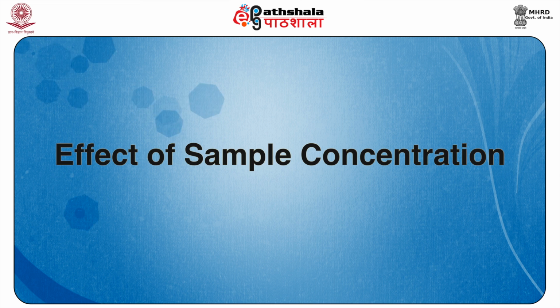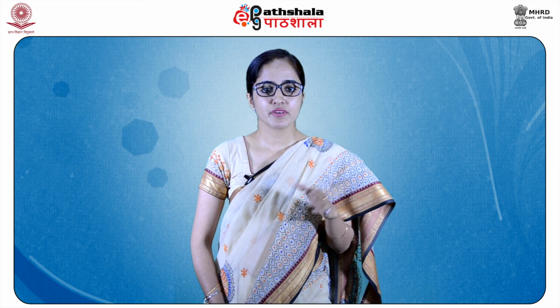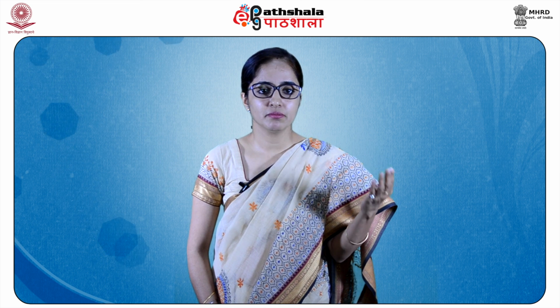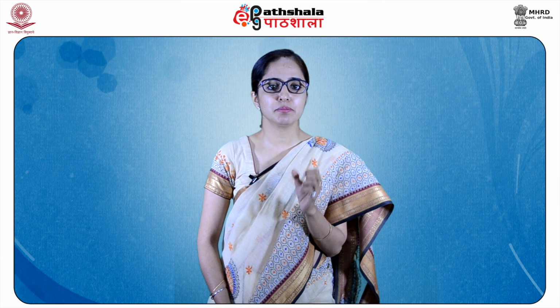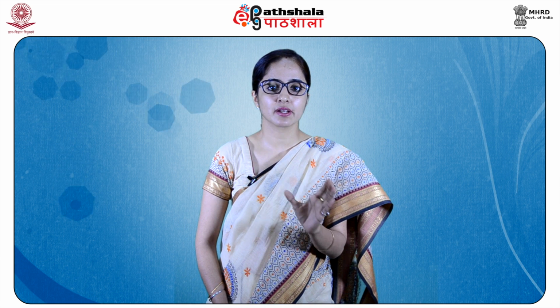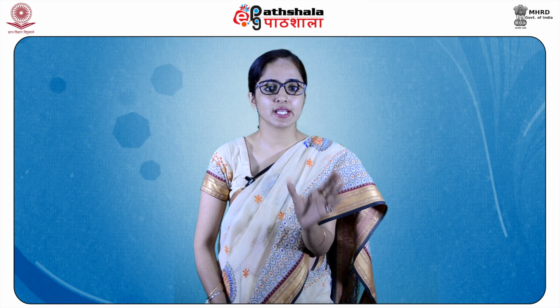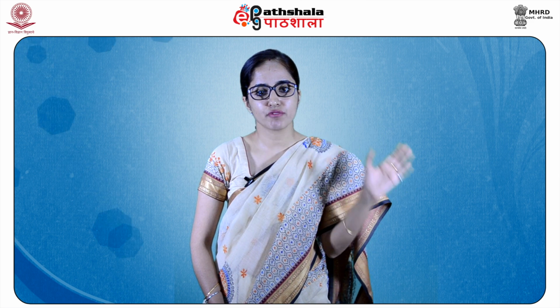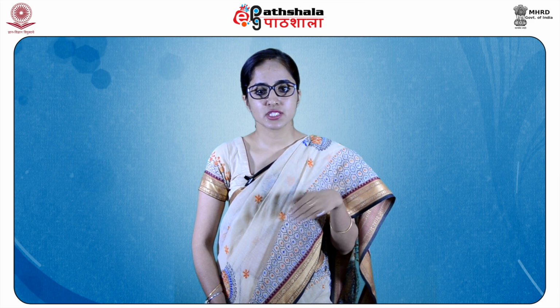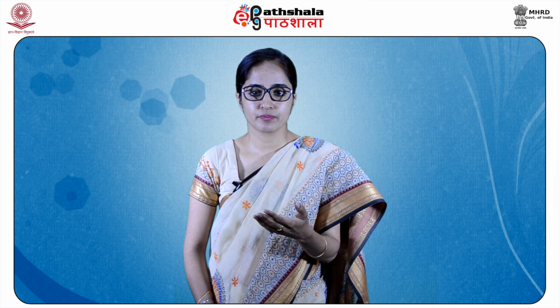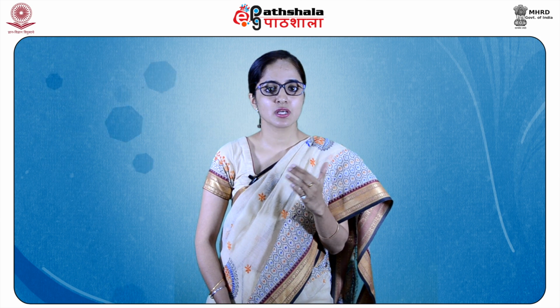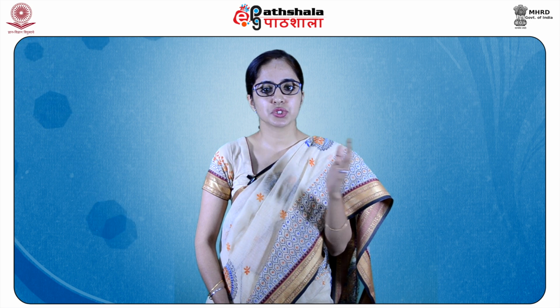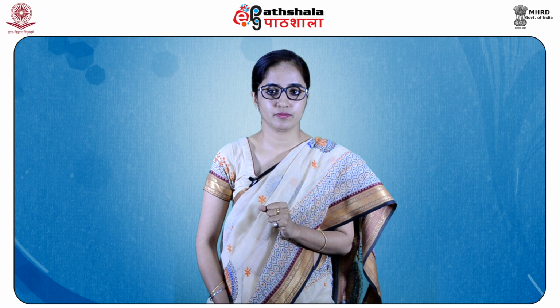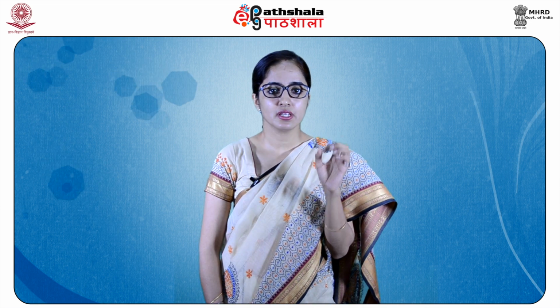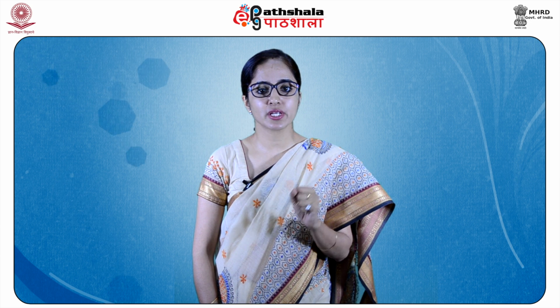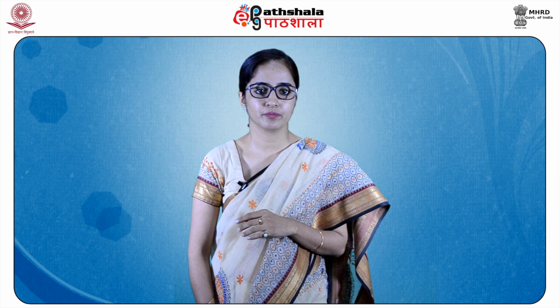Next comes the effect of sample concentration. We have studied the Lambert-Beer law and Lambert's law. According to the Lambert-Beer law, it might be expected that the sample concentration is directly proportional to the intensity of absorption. But as you increase the concentration of the solute, molecular interactions can take place, causing changes in the position and shape of the absorption bands. Such effects need to be identified and taken into consideration for quantitative work.